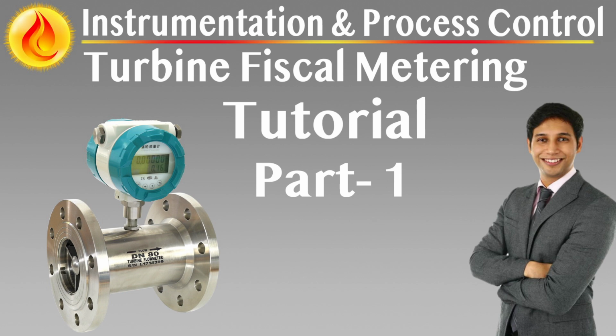Foundation for custody measurement chain. Because inlet header conditions are the baseline for all subsequent volumetric and mass flow calculations, errors or inconsistencies at this point can propagate through the entire measurement chain. The inlet header is therefore engineered as a high-integrity control point, equipped, verified, and installed to eliminate ambiguity and to satisfy both engineering and regulatory standards.